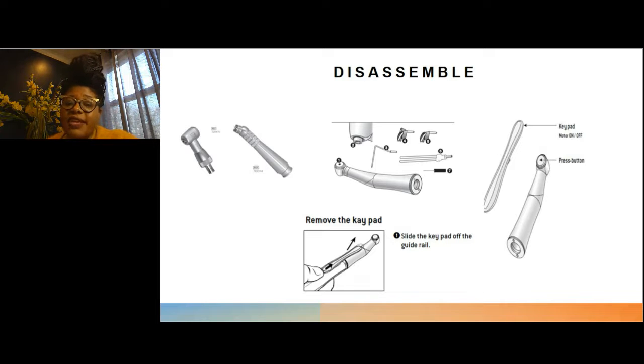Depending on which version or brand you have, some of the handpiece itself would come apart, but for this particular one, it was solid all the way through. And for the last one, the IFU is stating that the keypad needs to be removed, disassembled from the handpiece prior to commencing reprocessing.